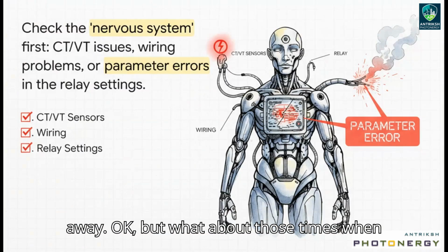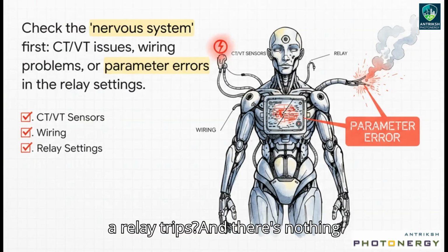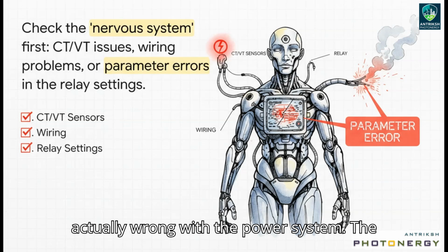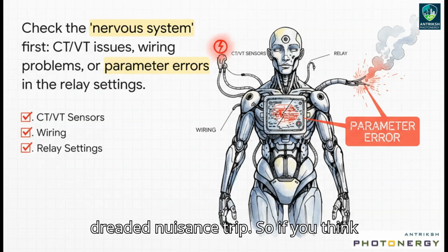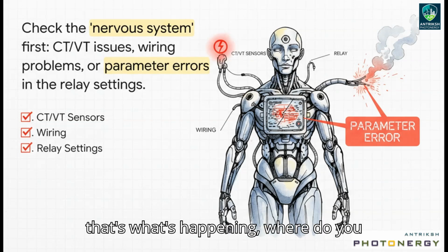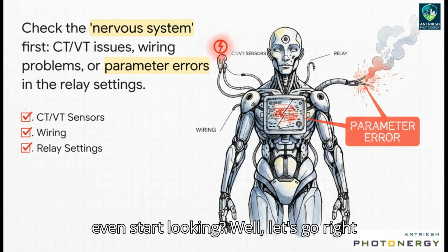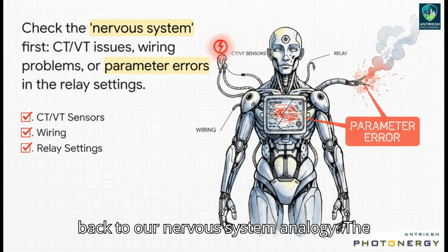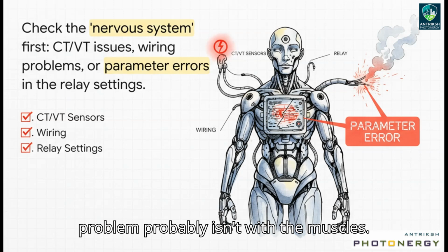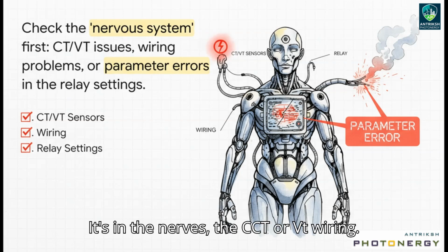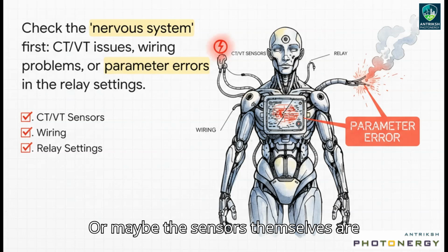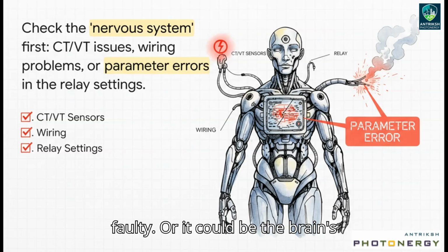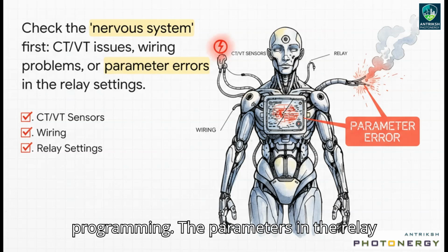Okay, but what about those times when a relay trips and there's nothing actually wrong with the power system? Ugh, the dreaded nuisance trip. So if you think that's what's happening, where do you even start looking? Well, let's go right back to our nervous system analogy. The problem probably isn't with the muscles. It's in the nerves, the CT or VT wiring, or maybe the sensors themselves are faulty. Or it could be the brain's programming. The parameters in the relay are just wrong.